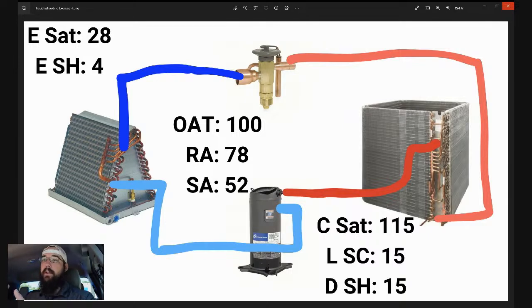What are some steps we can take to confirm it's an airflow issue? More than just we've taken refrigerant readings and we've got a strong suspicion it's an airflow issue. So what are our next steps? What do we do from here? How do we address that? Do we go static drop across the evaporator? Do we go fan speed, go straight to that? Okay, so yeah, take static, check coil visibly.